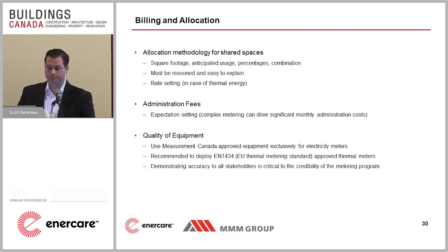the actual readings itself. Where you're deploying mechanical meters, water, and particularly thermal, we recommend using equipment that's built to the EN 1434 standard. That's the European standard that regulates the accuracy of thermal meters. We use exclusively a GWF product through our partner QMC. It's Swiss made. It's one of the best meters on the planet. So when you're going to talk to your customers, you want to be able to point to the quality of the equipment and the accuracy of that equipment.